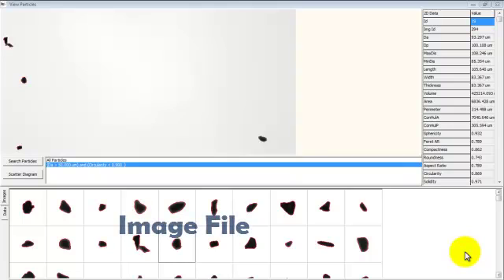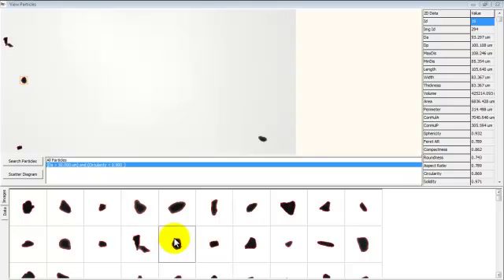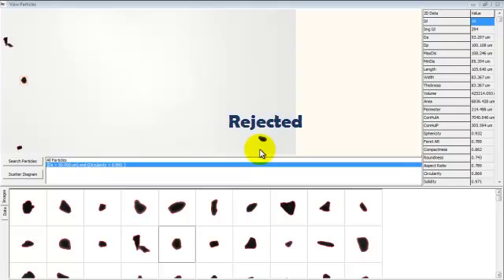This is a display of the complete image file, which can be scrolled through, and in the upper right is the list of all the size and shape parameters for the particle highlighted here in the image file. Note that all particles in the image file show a tight red boundary line around them, indicating they were on the focal plane and in focus. In the frame shot above, one of the particles is out of focus and is rejected, not included in the image file or the data.